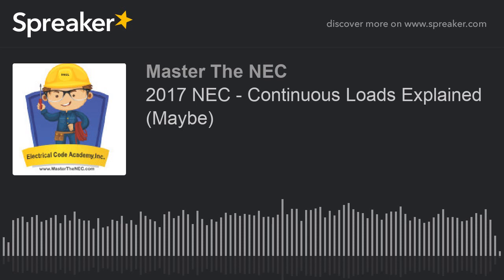It looks like a 12 is good for 30 amperes. Let me write that down: 30 amperes. Again, that's under 90, not under 75. Under 75, we notice that it's only good for 25 amps. We get that, and we know that we have to protect it at 20 amps. You with me? But we know that we can use this 30 amperes for our adjustment and corrections.